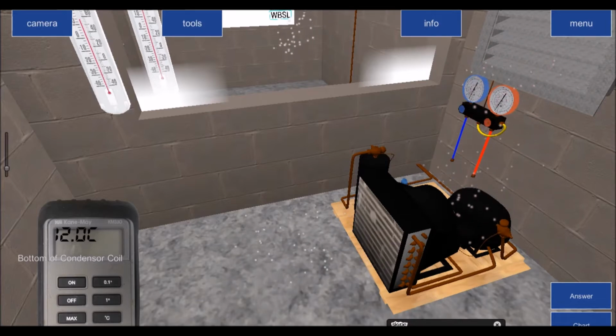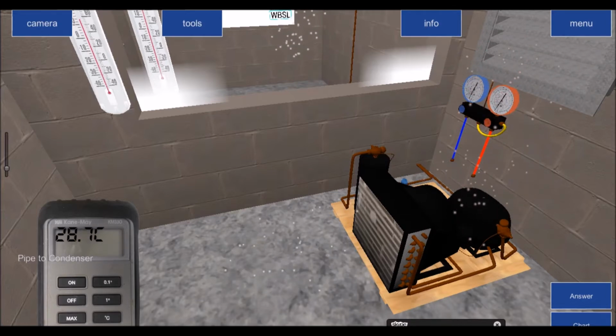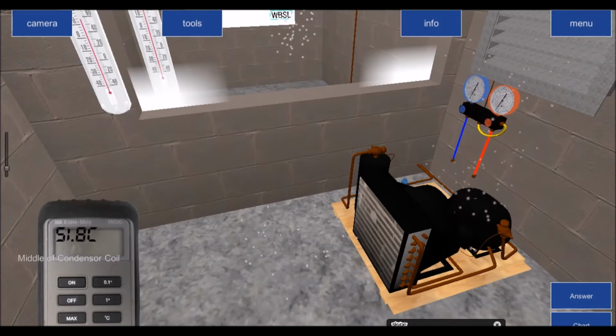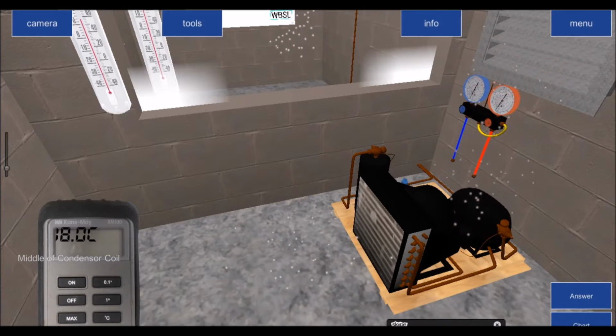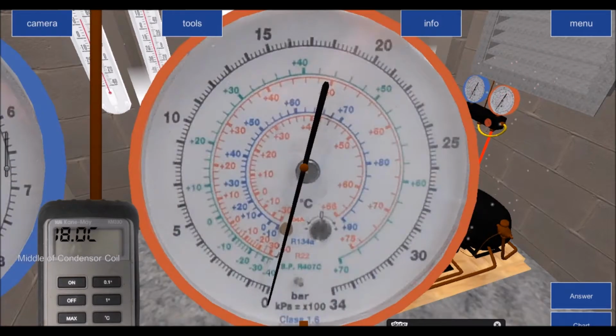So again, similar to what happened inside the evaporator, you've got high temperature, high pressure, superheated vapor being desuperheated in the first pass of the condenser. Then once it reaches its saturation temperature, it went from 70 something degrees through the condenser. Once it reaches its saturation temperature, which in this case is 18 degrees, it starts to condense from a high pressure, high temperature vapor to a high pressure liquid, and the pressure and temperature stay the same throughout. So this gauge line doesn't move.